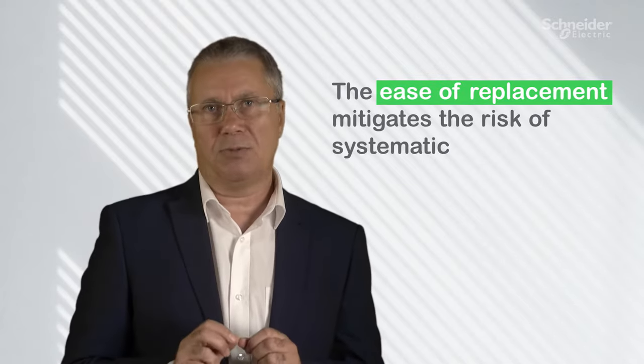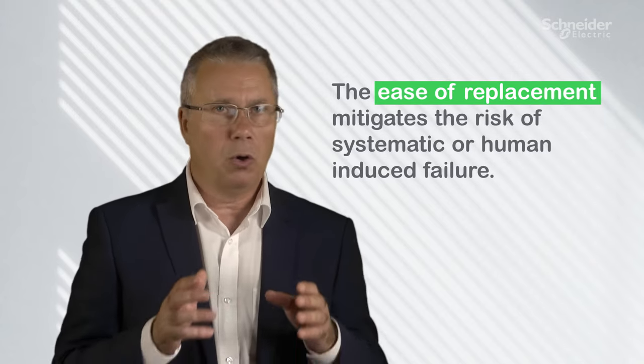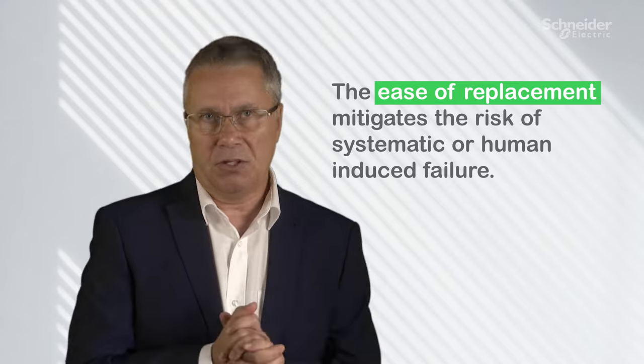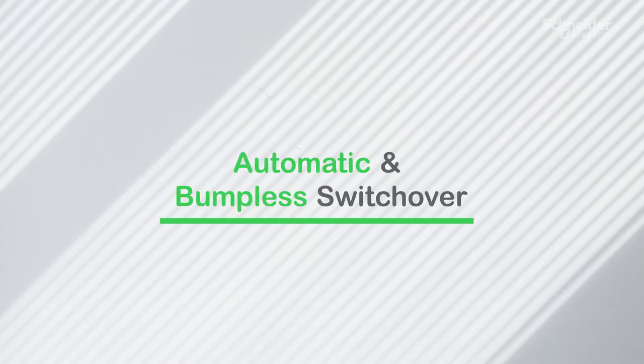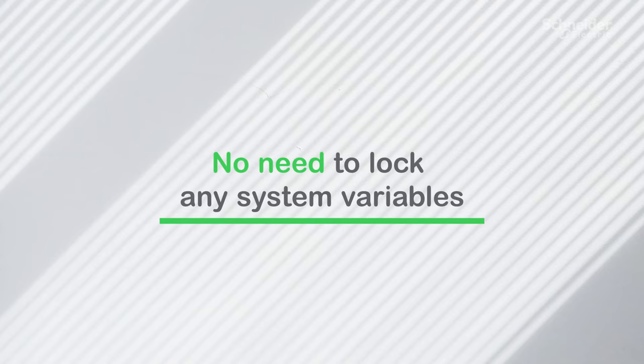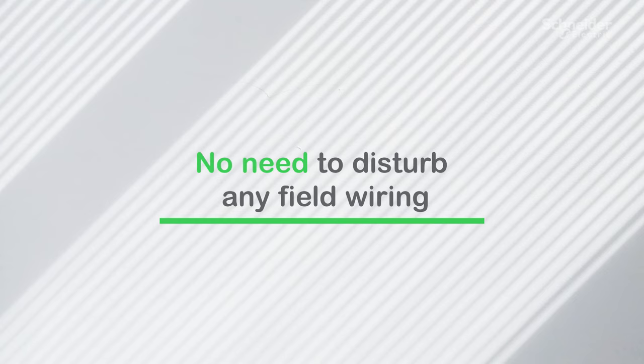This highly effective means of modular insertion and replacement is transparent to the operation of the system, and the ease of replacement mitigates the risk of any systematic or human-induced failure, as defined by safety standards such as IEC 61508. The switchover was automatic and bumpless. There was no need for any special programming, no need to lock any system variables, and no need to disturb any field wiring.